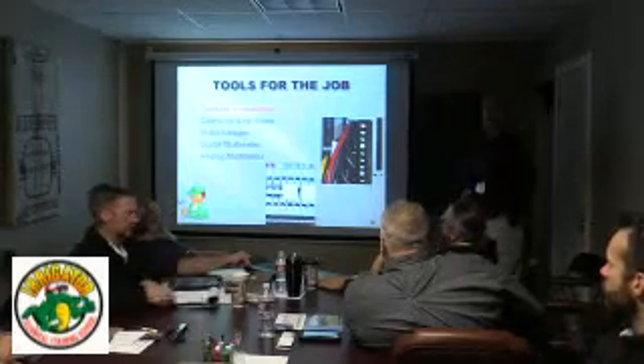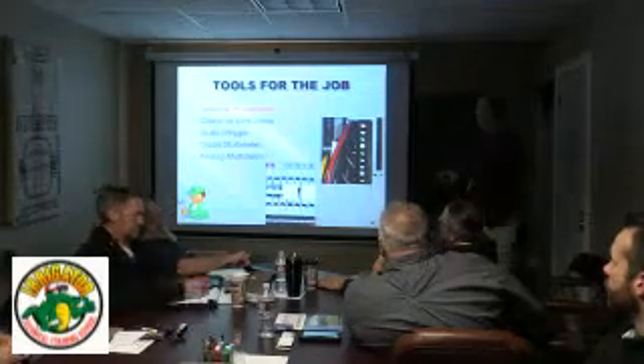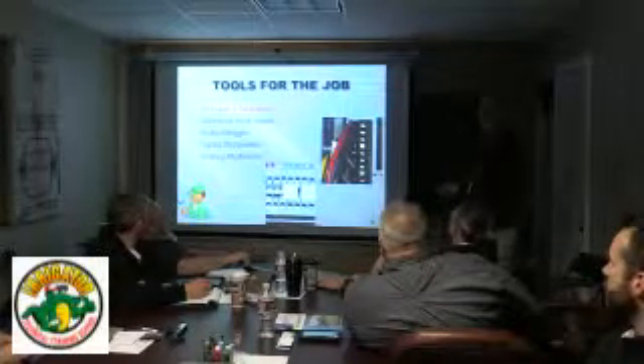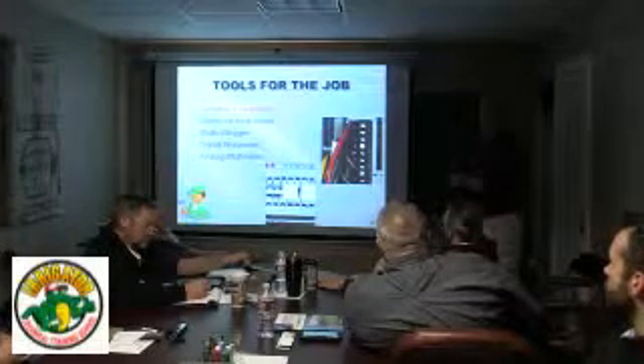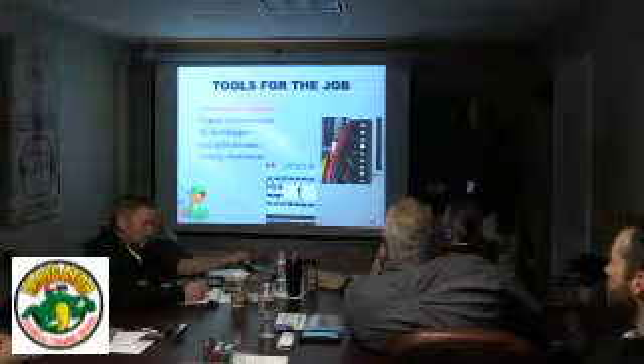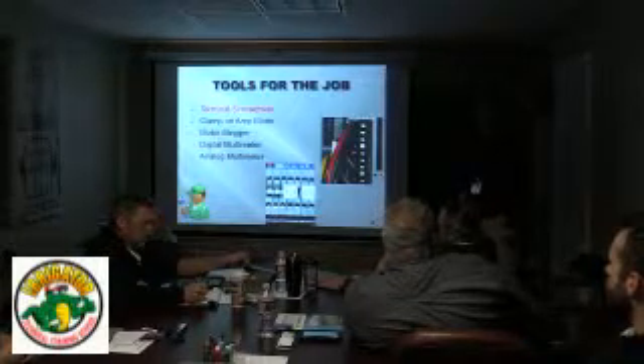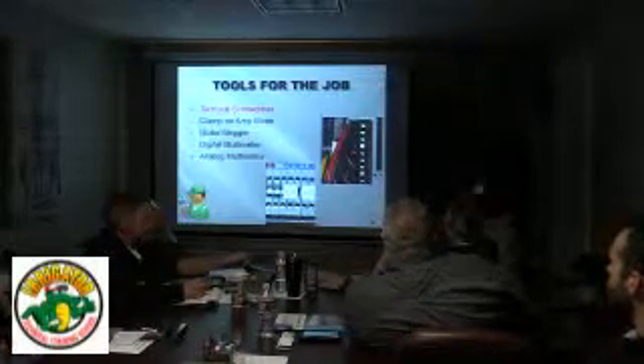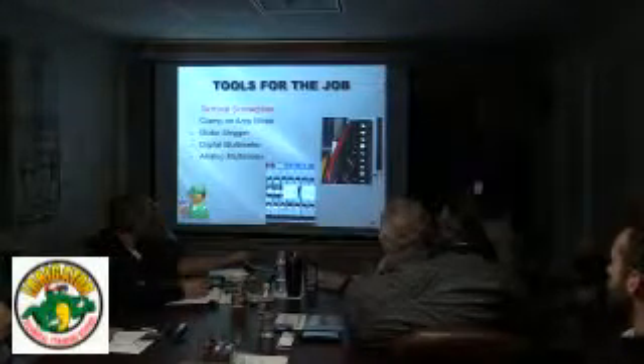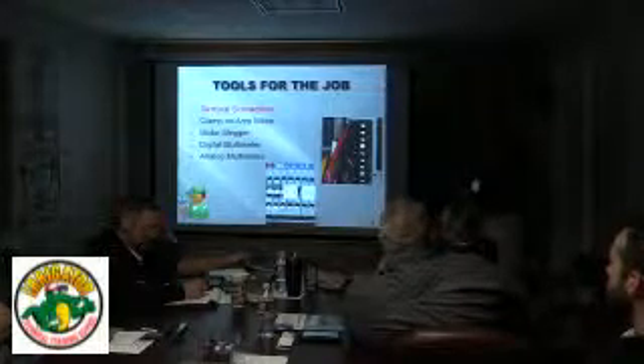Just real quickly on some of the tools for the job. A terminal screwdriver, you'll notice when you look in our panels, and I've got a couple of pictures here, the terminal block on a PLC, they're really small. We have a field terminal strip, we call it, at the bottom of all our panels. That's where all the field items come into. They've got small terminals too. I get a lot of calls every year that they have to go find a screwdriver and call me back because they can't get to those. So if you are going to do startups or work on these or basic troubleshooting, it's about 1/8 inch wide at the bottom. Make sure you have one of those.